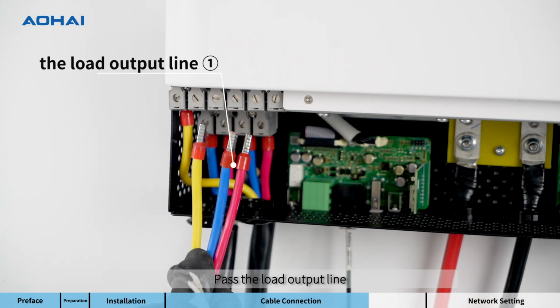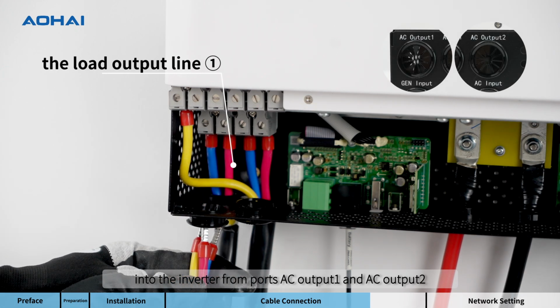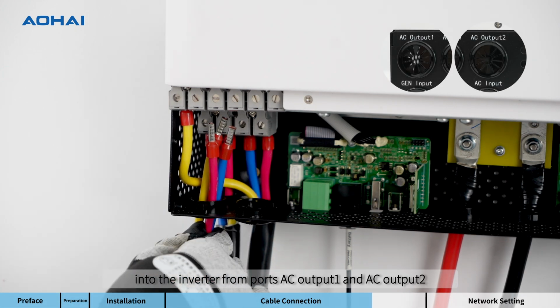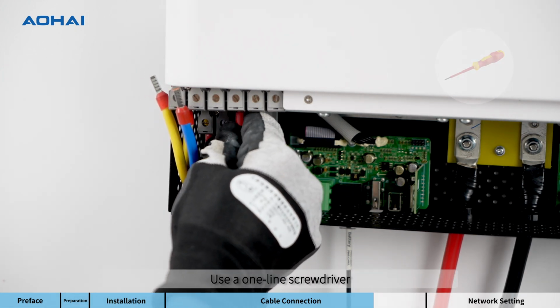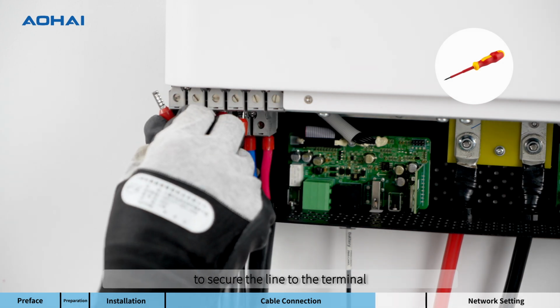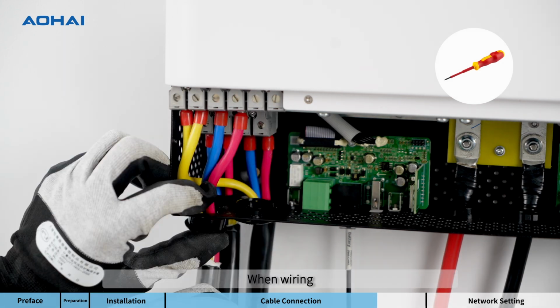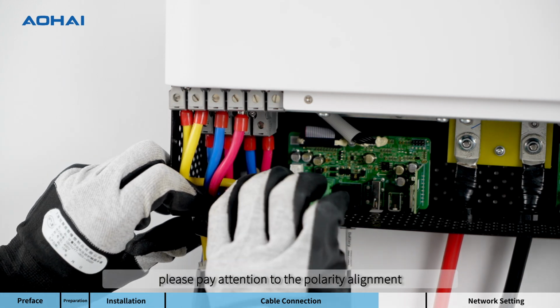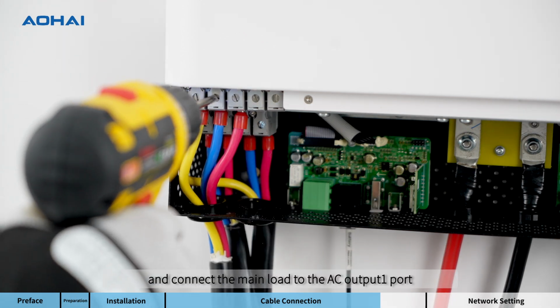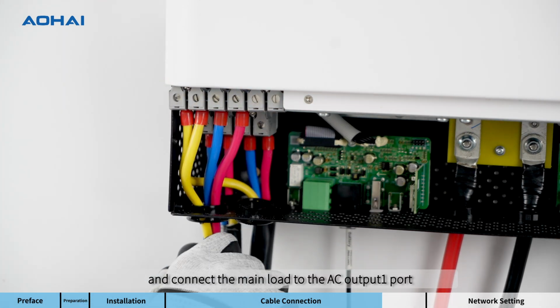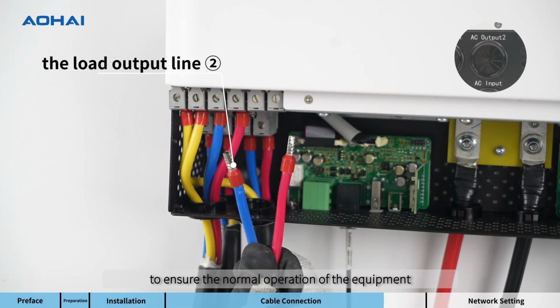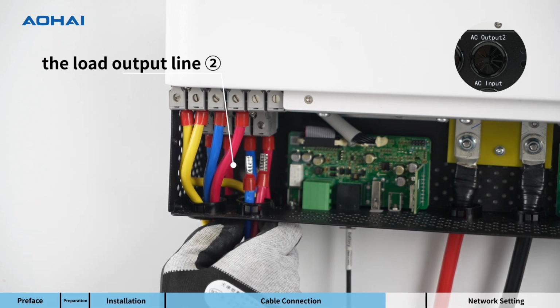Pass the load output line into the inverter from ports AC output 1 and AC output 2, respectively. Use a single-slot screwdriver to secure the line to the terminal. When wiring, please pay attention to the polarity alignment and connect the main load to the AC output 1 port to ensure the normal operation of the equipment.